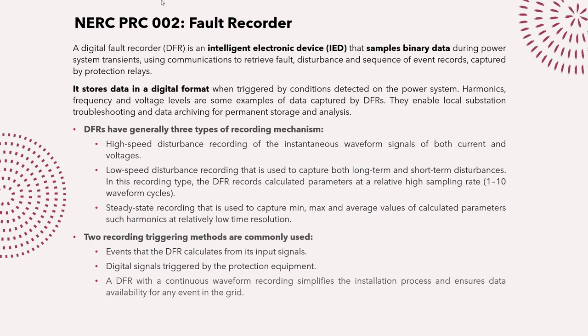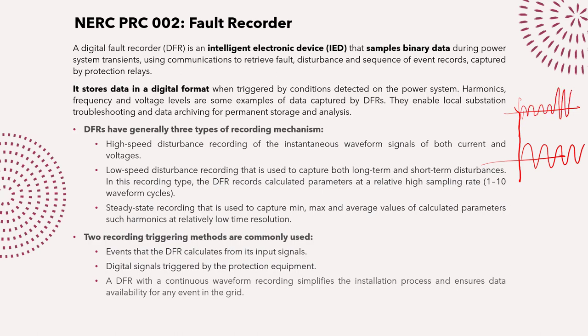Fault recorders have three types of recording mechanisms. The first is high-speed disturbance recording of instantaneous waveform signals of both current and voltage. For example, the voltage waveform is captured continuously; when a fault occurs, the fault current increases and the voltage suddenly drops significantly. After fault clearance, the voltage changes depending on the fault type. This mechanism records the instantaneous waveform signals of both current and voltage.